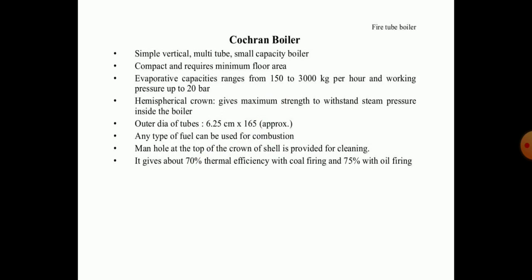The outer diameter of the tubes must be approximately 6.25 centimeters. Any type of fuel can be used for combustion, and a manhole at the top of the crown of the shell is provided for cleaning. It gives about 70 percent thermal efficiency with coal firing.